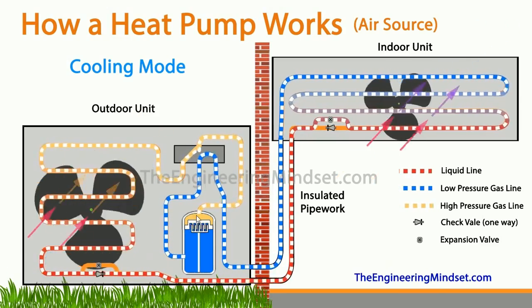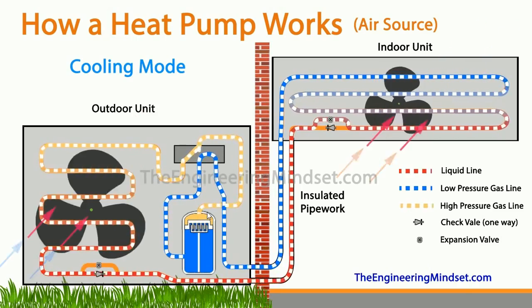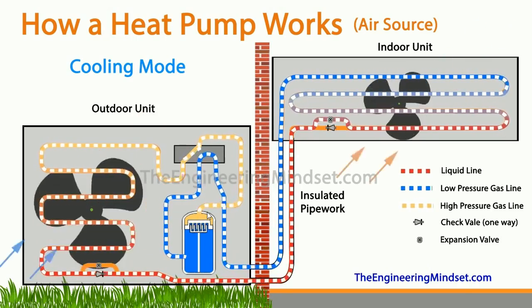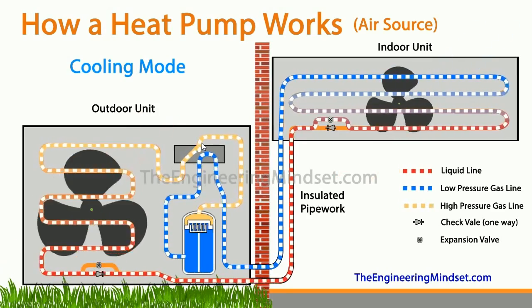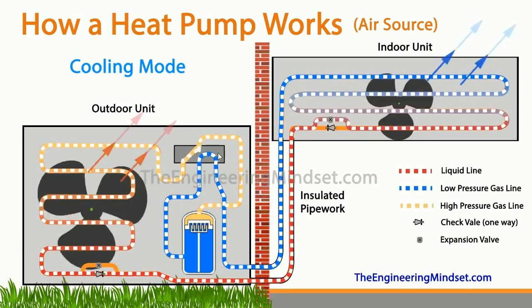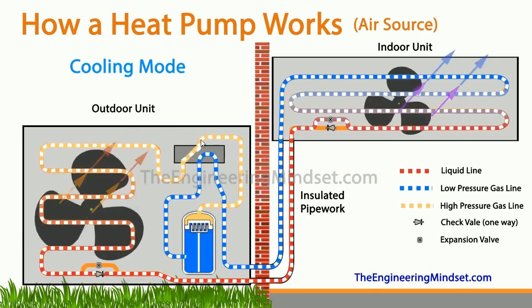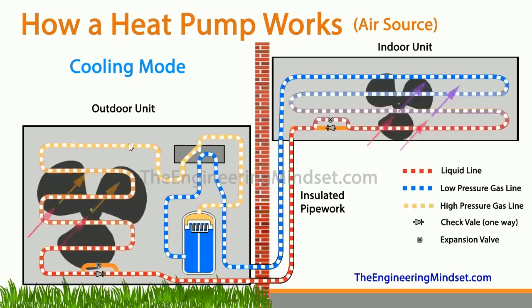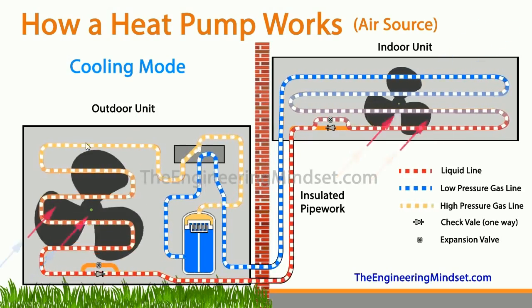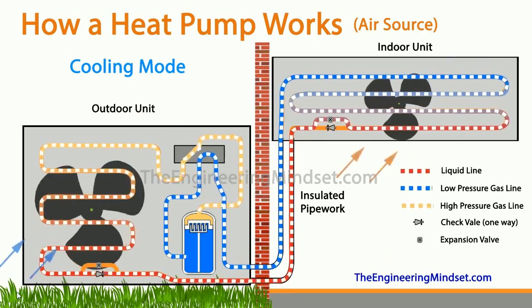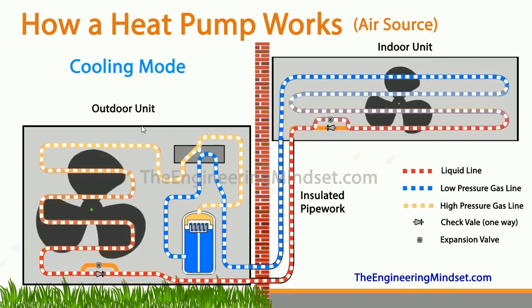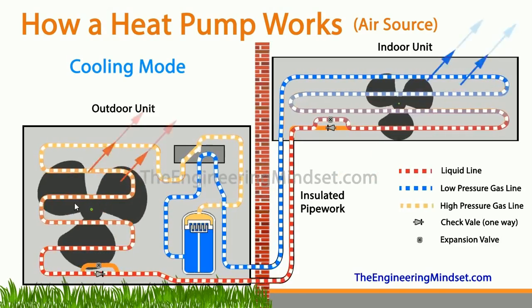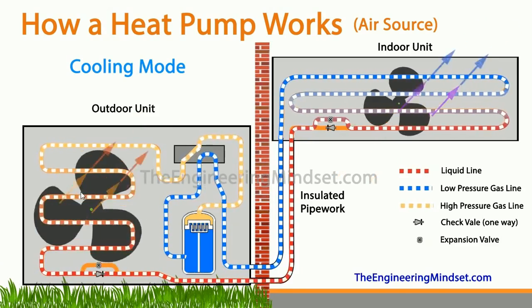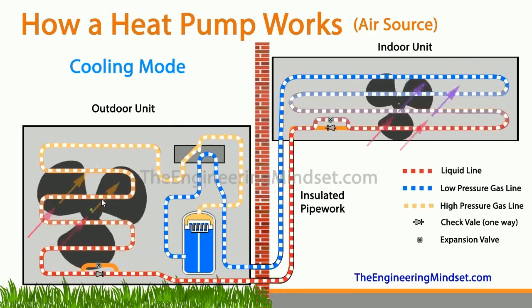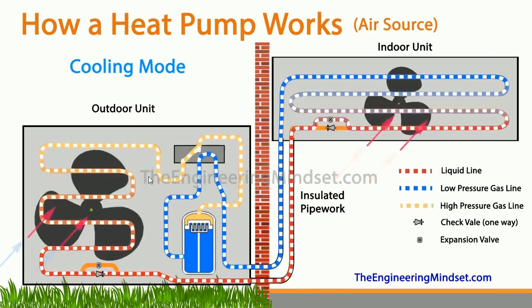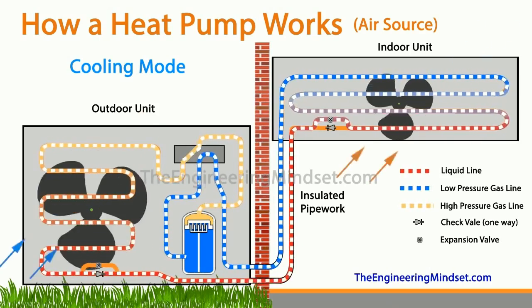Now the refrigerant is leaving the compressor here, and that's leaving as a high pressure, high temperature saturated vapor, and that heads off straight up into the top of the reversing valve, where the reversing valve will decide which direction it can flow to. And in this case it's being diverted and sent straight to the outdoor heat exchanger, where the refrigerant will be condensed and it will give up some of its energy. And you can see these arrows here showing that there is air being pulled in by this fan, the outdoor air, which is cooler than the temperature of the refrigerant inside the tubes, and some of that energy will be taken away to allow this refrigerant to condense.